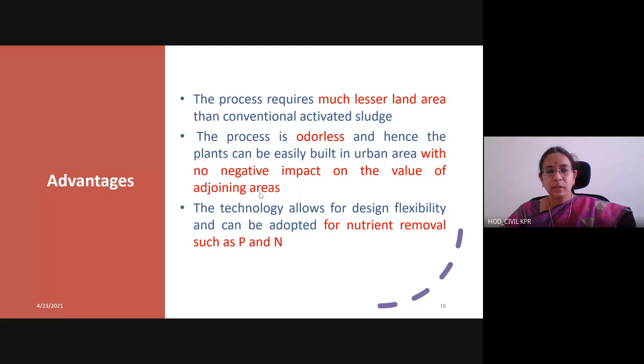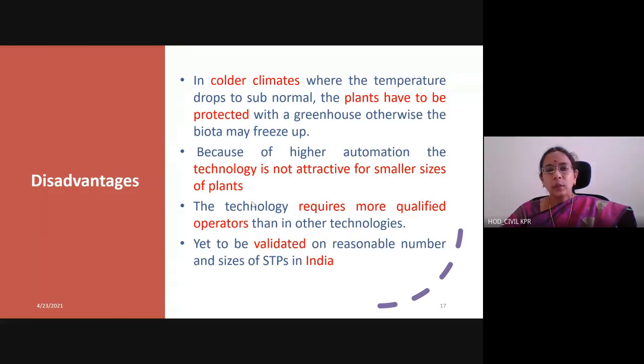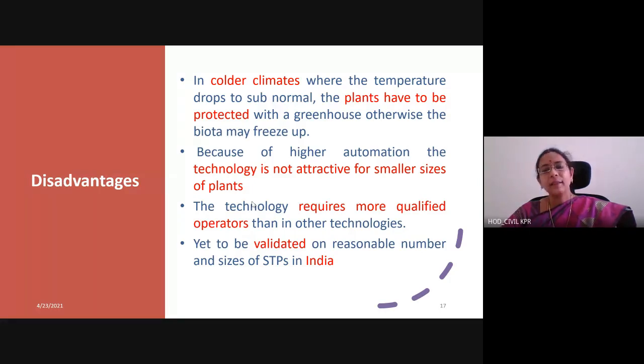The advantages of the FBBAS process are that it requires much less land area than conventional activated sludge. This process is odorless and hence plants can be easily built in urban areas — it can be used in localities with high human population since it has no negative impact on adjoining areas. It is well adapted for nutrient removal such as phosphorus and nitrogen, which is of major importance. In colder climates, since temperature is abnormal, the greenhouse can protect the plants. Disadvantages include that because of higher automation, the technology is not attractive for smaller sites. It requires more qualified operators than other technologies, and this process is not yet validated in India — it is being used abroad but not yet domestically.